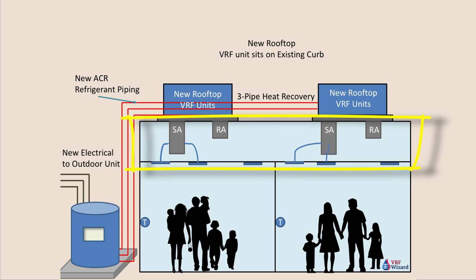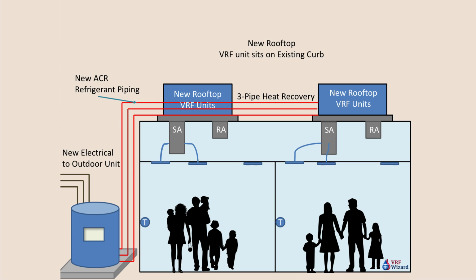You now don't have to worry about running outside air ducts through the attic or trying to get your minimum air to the VRF indoor units, because now your indoor unit is actually in the package unit on the roof, which has access to the outside air, so your ventilation is available.